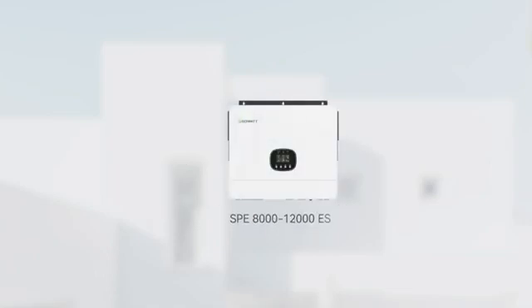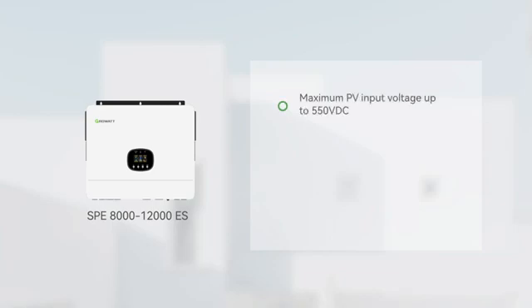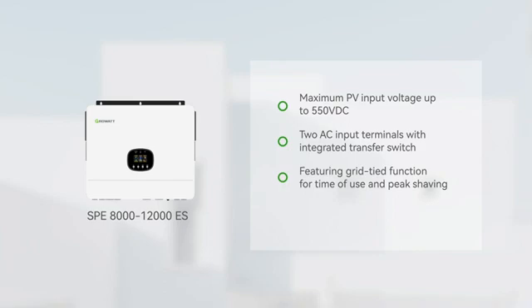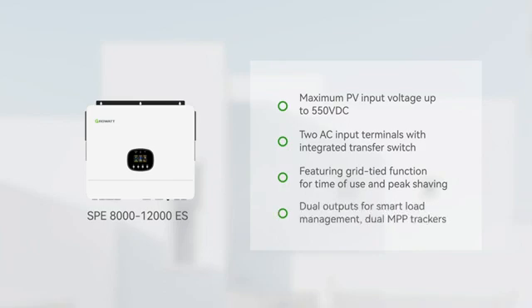SPE-8000-12000ES inverter key features: maximum PV input voltage up to 550 VDC, two AC input terminals with integrated transfer switch featuring grid-tie function for time of use and peak shaving, dual outputs for smart load management, and dual MPP trackers.